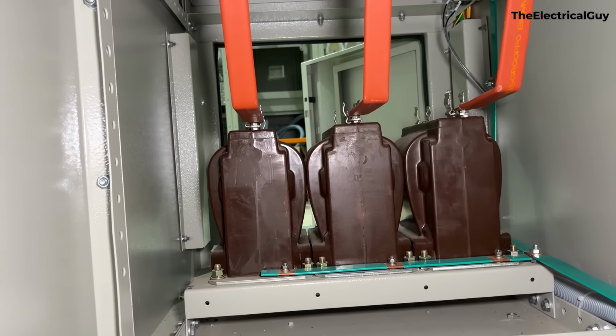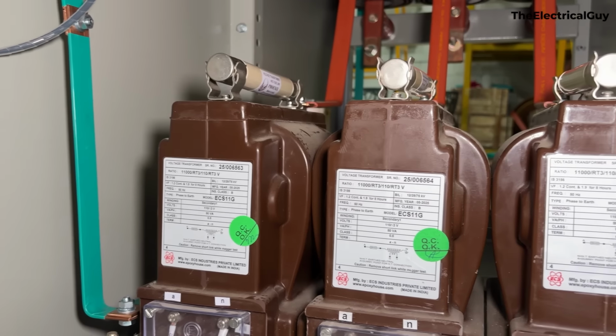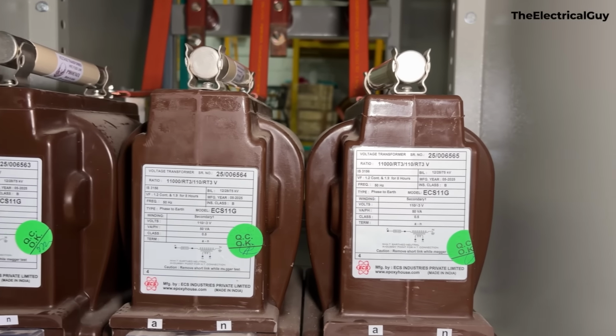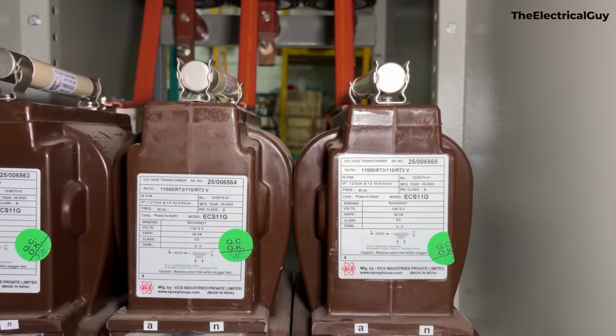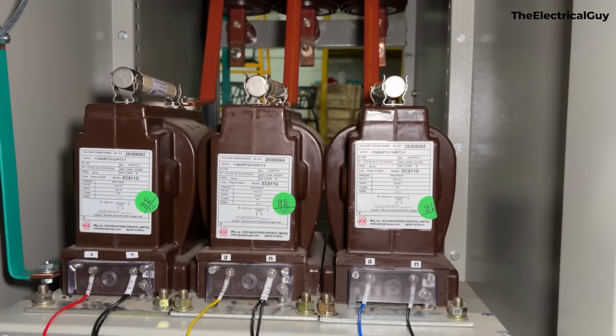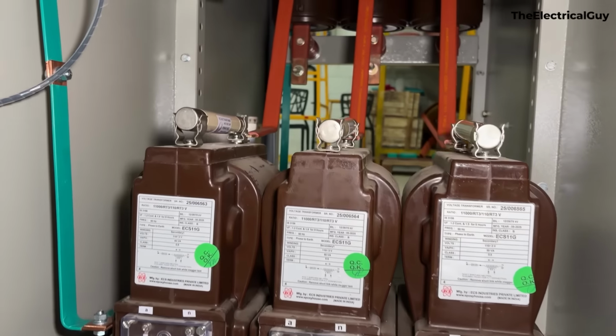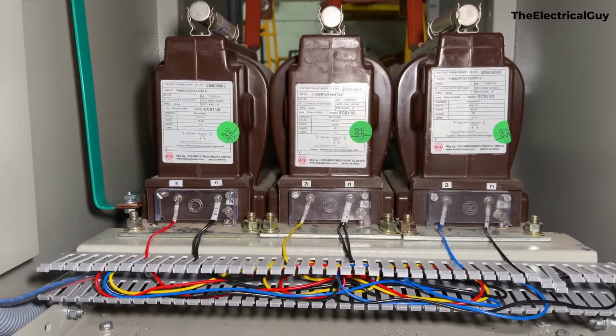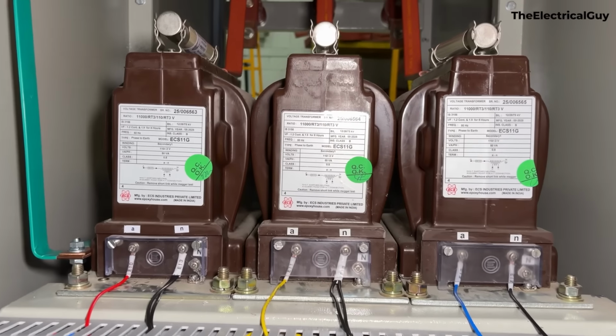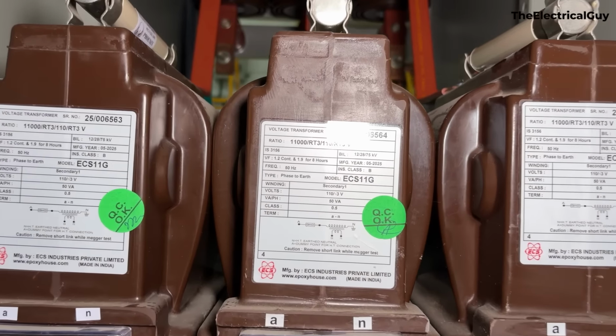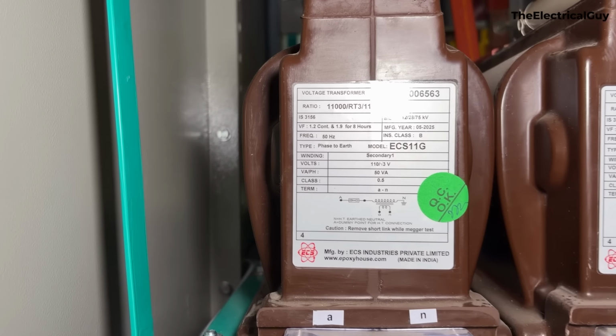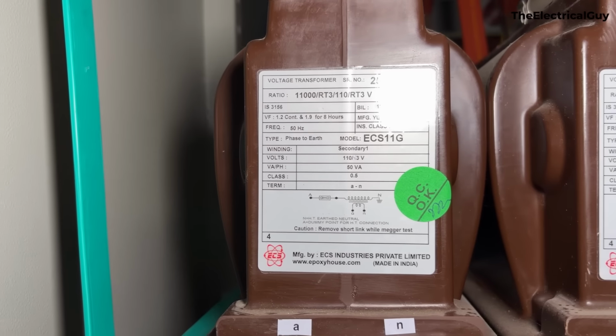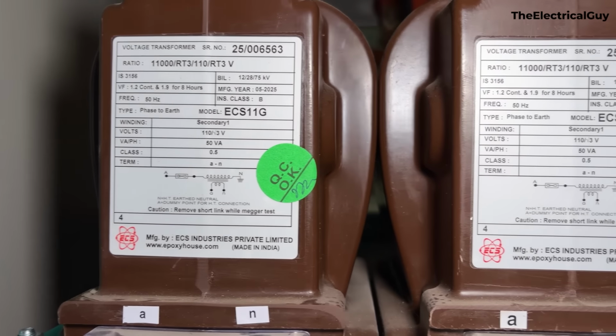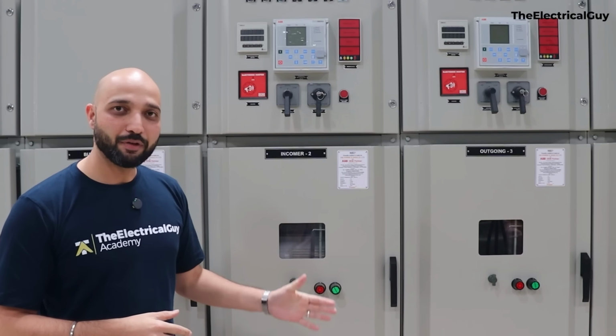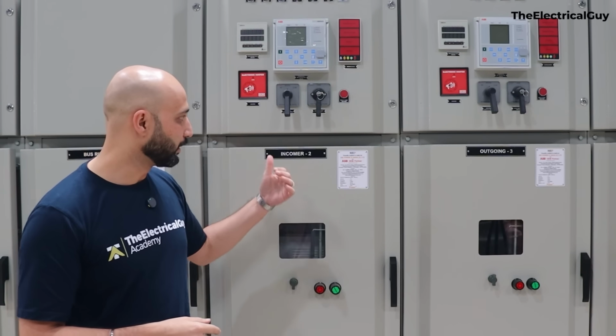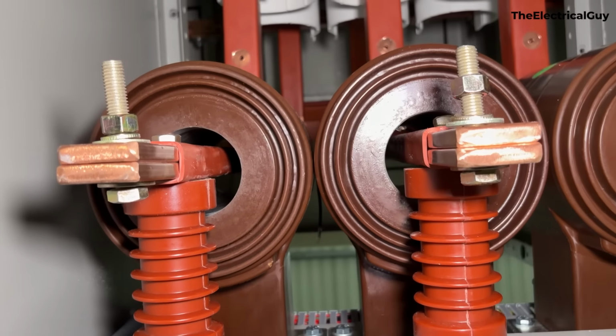There is an arrangement where the cables can be entered, and after that you will see a voltage transformer connected, which is connected in parallel with our system, and high tension fuses are also connected. So in case the current increases, we need something to protect our transformer, right? So those fuses will help us in doing that, and it's a single core voltage transformer. You can see the rating plate as well there.